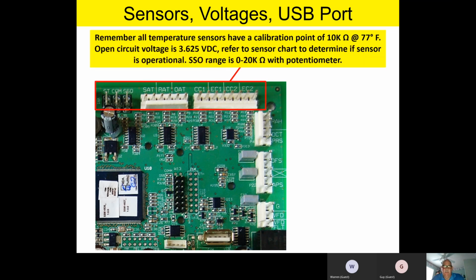All right, team. Now remember, all temperature sensors have a calibration point of 10,000 ohms at 77 degrees. Open circuit voltage: in other words, if I remove the harness from any of these sensors and take the voltage on the pins where those sensors hook up, it should be 3.625 volts DC. And then again, we could refer to that sensor chart we talked about to determine if the sensor is operational. And as the last little point, remember, if you have an optional SSO sensor, a space offset, it's 0 to 20,000 ohms with that potentiometer or variable resistor.